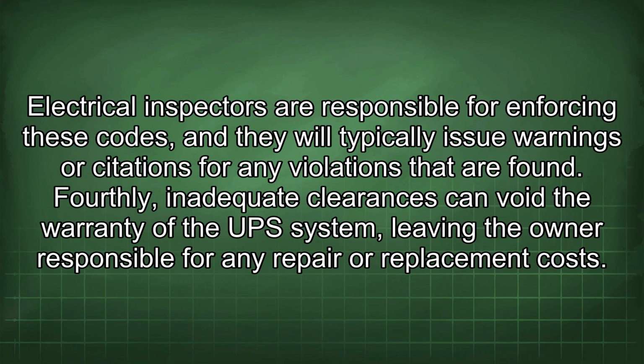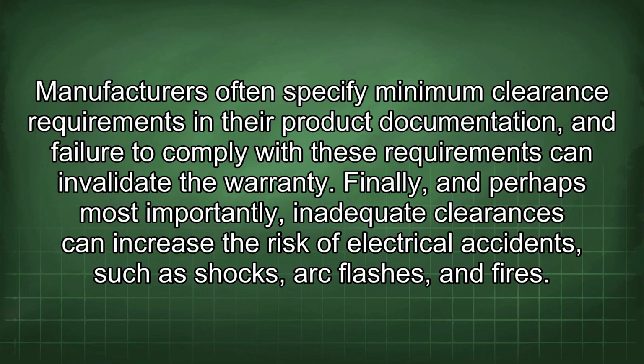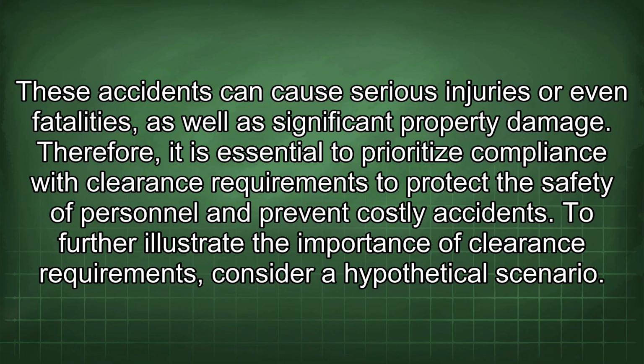Electrical inspectors are responsible for enforcing these codes, and they will typically issue warnings or citations for any violations that are found. Fourthly, inadequate clearances can void the warranty of the UPS system, leaving the owner responsible for any repair or replacement costs. Manufacturers often specify minimum clearance requirements in their product documentation, and failure to comply with these requirements can invalidate the warranty. Finally, and perhaps most importantly, inadequate clearances can increase the risk of electrical accidents such as shocks, arc flashes, and fires. These accidents can cause serious injuries or even fatalities, as well as significant property damage. Therefore, it is essential to prioritize compliance with clearance requirements to protect the safety of personnel and prevent costly accidents.